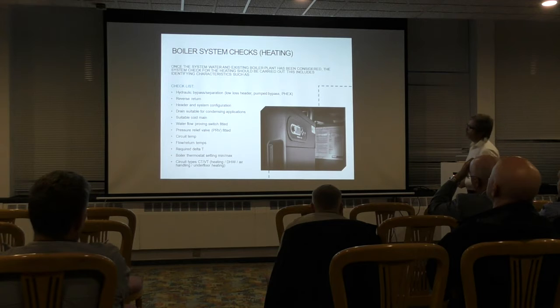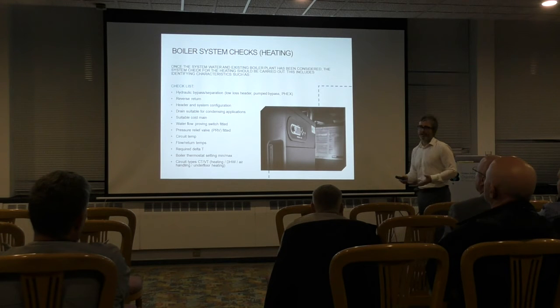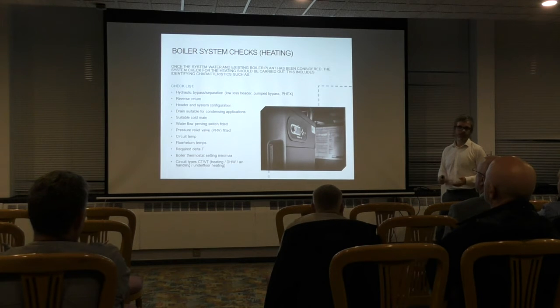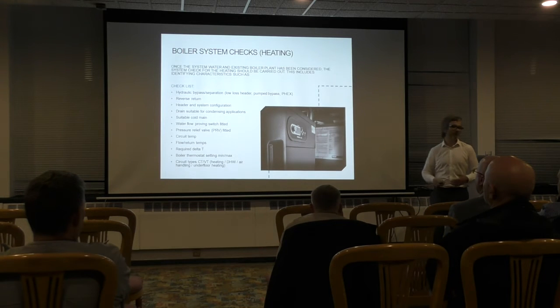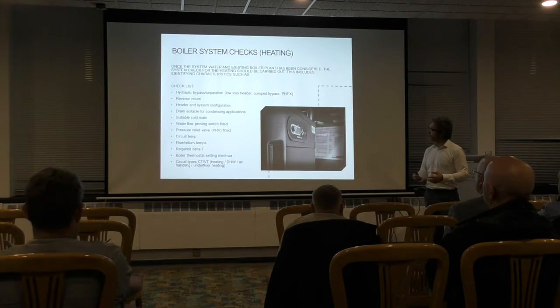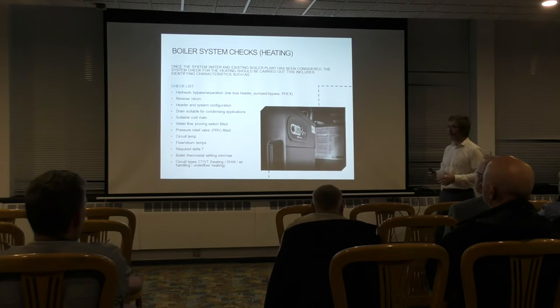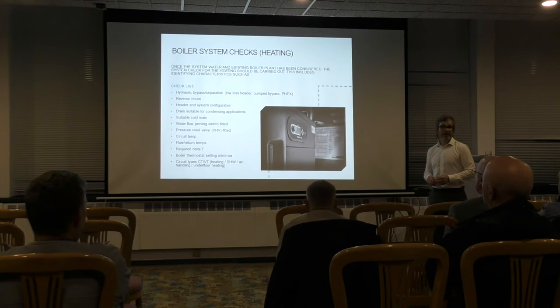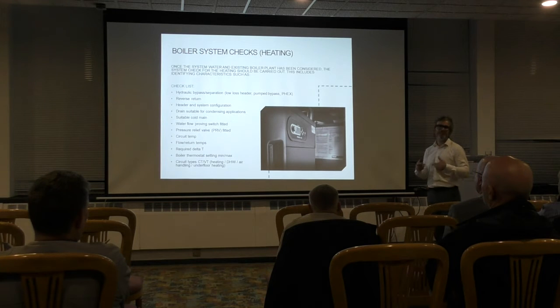Also, because now we're probably looking at putting a condensing boiler in, we need to be able to drain that condensate away to a suitable drain point. Hopefully in the plant room there will be a drain or a sump or something that you can drain that away to. If you haven't got it, it's not the end of the world, because we can supply you a condensate pump, and that pump will pump the condense away to a suitable location. But you want to try and avoid that, I suppose, because again, it's another moving part in the boiler house, which potentially could go wrong.